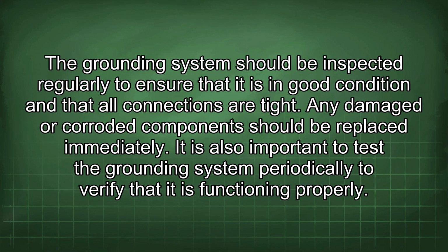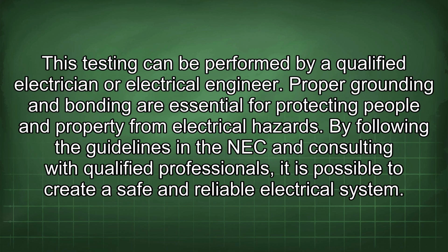The grounding system should be inspected regularly to ensure that it is in good condition and that all connections are tight. Any damaged or corroded components should be replaced immediately. It is also important to test the grounding system periodically to verify that it is functioning properly. This testing can be performed by a qualified electrician or electrical engineer. Proper grounding and bonding are essential for protecting people and property from electrical hazards.